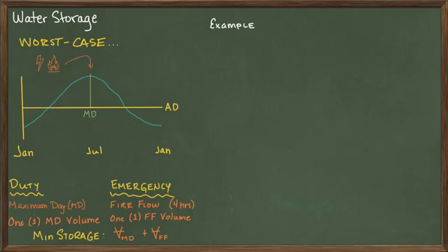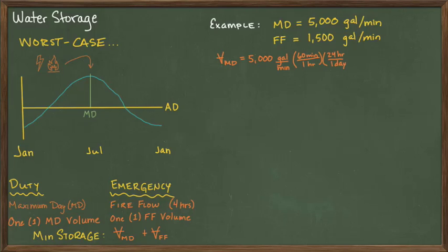Let's assume that we just finished computing the water demand for a large community. The maximum day demand for this community is 5,000 gallons per minute. And based upon the structures that we are building in the neighborhood, we have a minimum fire flow of 1,500 gallons per minute. The volume of the maximum day demand after 24 hours of flowing is computed as 5,000 times 60 minutes per hour times 24 hours in a day. And this gets us 7.2 million gallons required just for the duty storage of one max day demand.